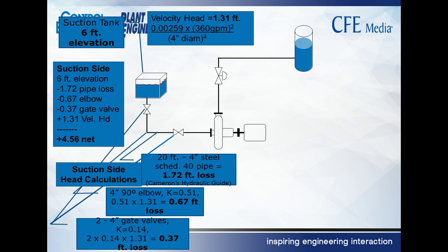Let's just go through that quickly. Here on the suction side, we've got 6 feet of elevation, so we've got 6 feet of head coming into the pump. That's helping us. That's a positive. Okay. We have to develop some velocity head. We've got to get that liquid moving, and that's going to cost you 1.3 feet of head. We've got some friction through some pipe. 20 feet of 4-inch steel pipe loses 1.7 feet. We've got an elbow. We lose a half a foot through the elbow or so, and a couple of isolation valves through which we lose a total of about 0.3 of a foot. Okay, well, let's total that all up. We started with 6. We had to take off some friction.